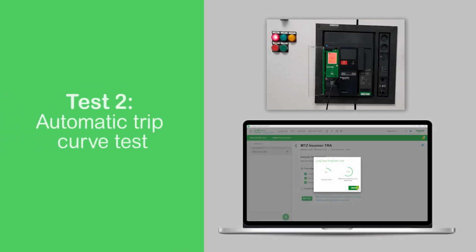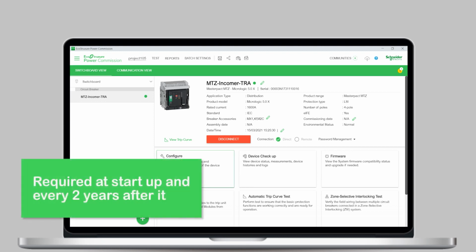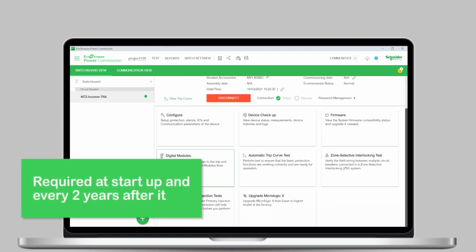Well, now let's move to another test function, automatic trip curve test. It is actually equivalent to the so-called secondary injection test that is required at startup or for preventive maintenance purpose. You can prove to your customers that the breaker can actually trip according to the pre-configured protection settings inside Micrologic. We strongly recommend performing such tests with a report every 2 years as part of the preventive maintenance program.